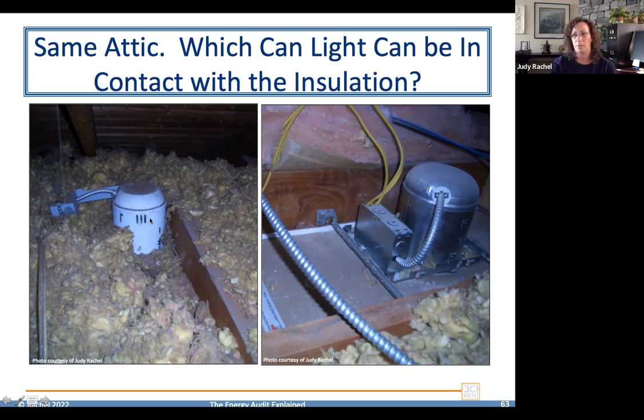because a model number should be inside the actual fixture itself, the luminaire, to find out whether it can be in contact. And that's the same with this one. You start to suspect, looking at this one, it is very typical, the look of an insulation contact airtight can, but once again, you need to confirm that. And obviously these were in the same attic, and it was completely the opposite of what should be happening.